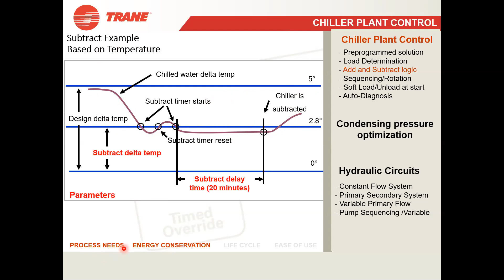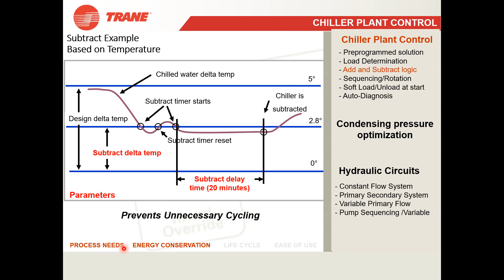So by doing this, you are actually meeting the process needs. Your load side is never hampered. You are always supplying the required temperature, keeping the room at 24 degrees or whatever set point you have set, and at the same time you are conserving energy. So this definitely prevents unnecessary cycling, while still meeting process needs and achieving energy conservation.